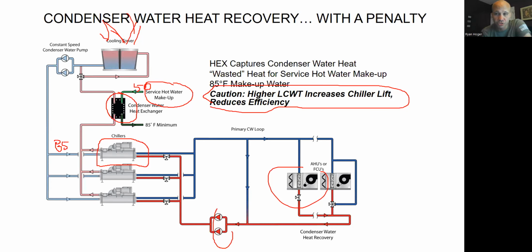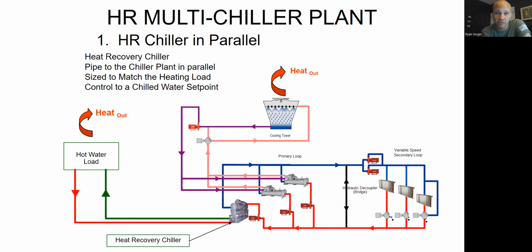So we have a couple of solutions to that that involve what I'm going to call a heat pump chiller, or heat recovery chiller, or heat reclaim chiller. HR in this case means heat recovery or heat reclaim. So what I'm going to do, same idea. I got all these air handlers over here on the chilled water side, right? I got my two chillers, got my cooling tower. Instead of adding a heat exchanger on this water and then sending it over to my domestic water, I'm going to add a chiller onto there.